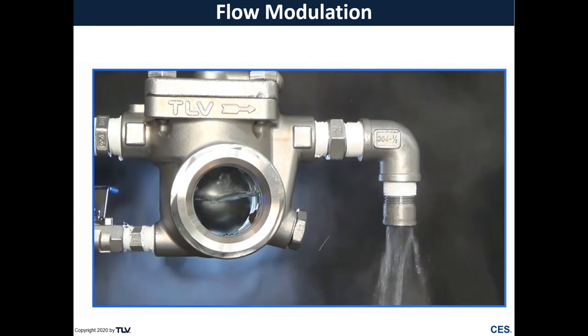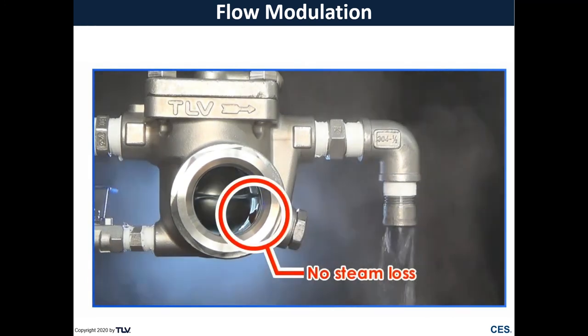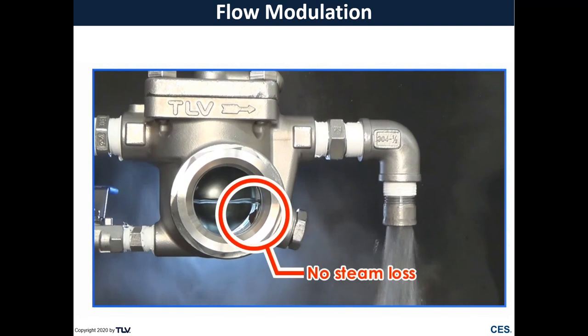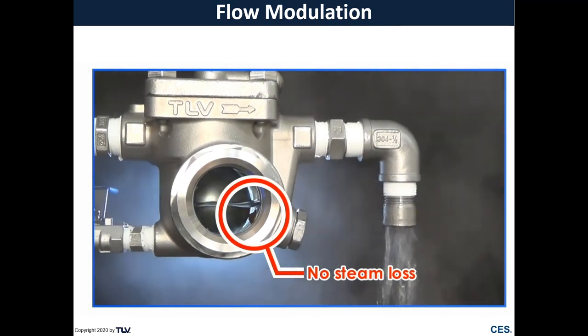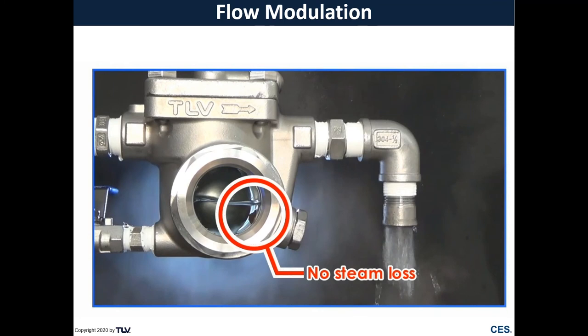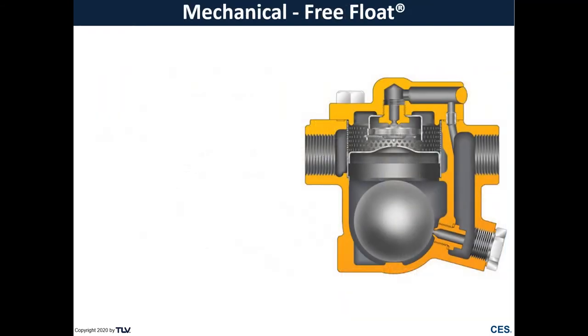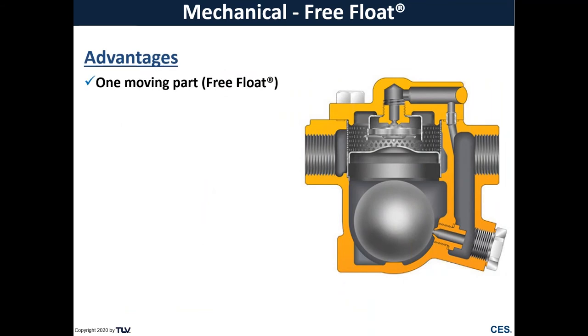So because this float has to become buoyant, there always is, under normal operation, a liquid level. And the benefit to this is that orifice never really sees live steam. And so there's really no way for live steam to leak through this orifice during normal operation. Some of the advantages to this trap type is there's a single moving part. The only moving part in this trap is that free float, and it's continuously rotating to give you a brand new seating surface.